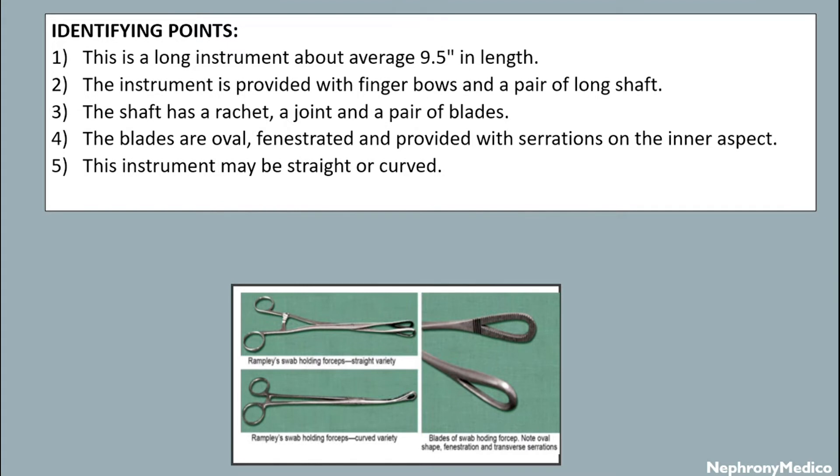The instrument is provided with finger bows and a pair of long shafts. The shaft has a ratchet joint and a pair of blades. The blades are oval, fenestrated, and provided with serrations on the inner aspect.